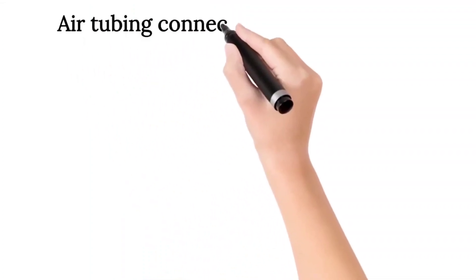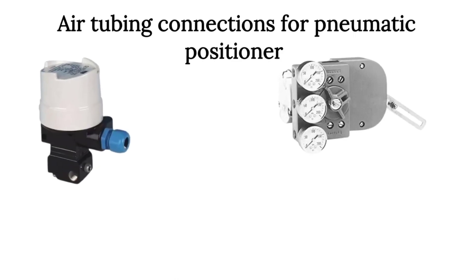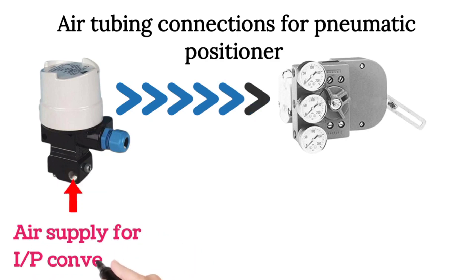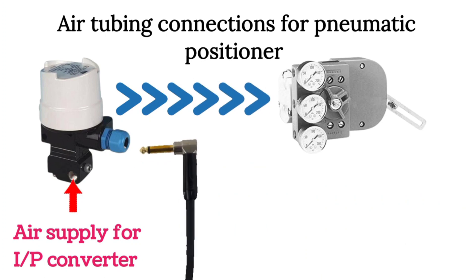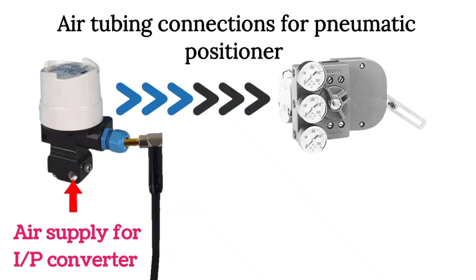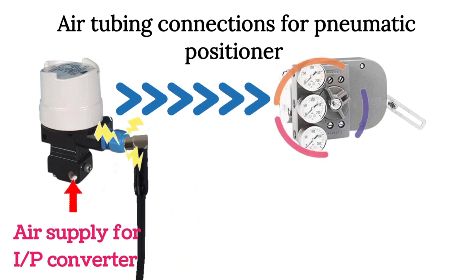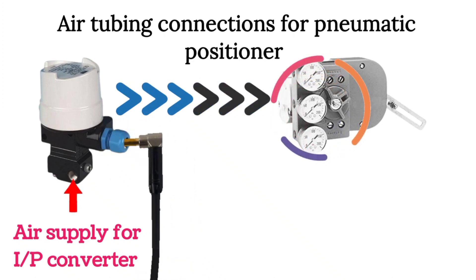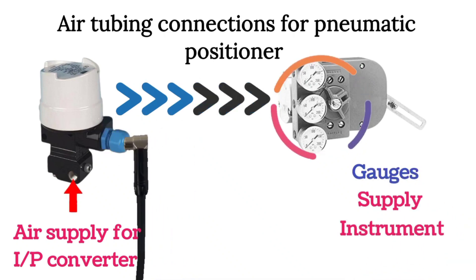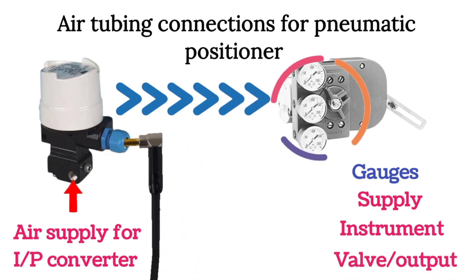Now I will explain air tubing connections for the pneumatic positioner. An I2P converter is used to control the pneumatic positioner. Air supply for the I2P converter is shown in the image by the arrow. A 4 to 20 milliampere electrical signal is fed here. We use two wires for connections — one is connected at the positive terminal and one at the negative terminal. In the circle, three pressure gauges are shown: one gauge is for air supply, usually labeled 'instrument.' The I2P converter output is connected at this port. One gauge is for control valve air or output air, and this port is connected at the control valve.